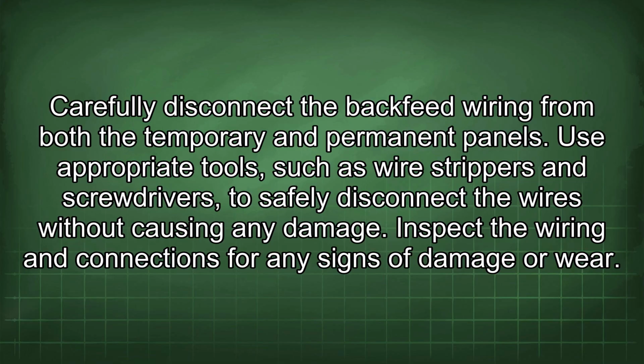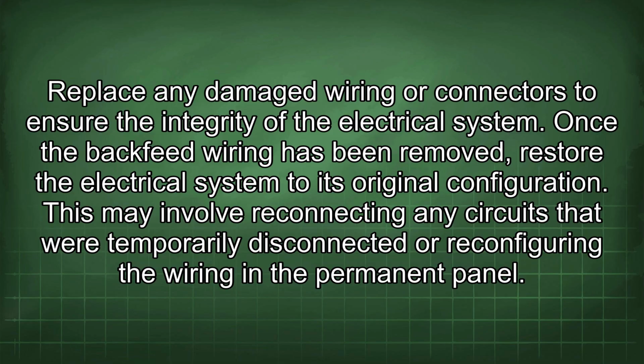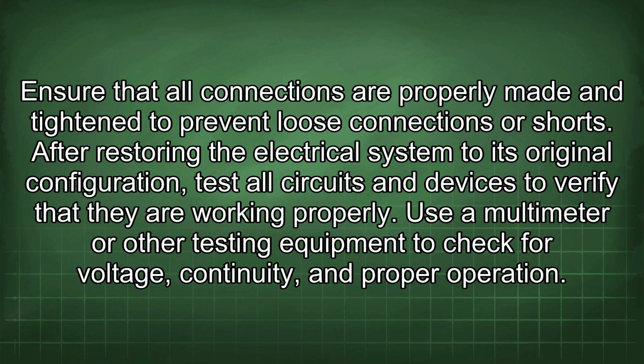Inspect the wiring and connections for any signs of damage or wear. Replace any damaged wiring or connectors to ensure the integrity of the electrical system. Once the backfeed wiring has been removed, restore the electrical system to its original configuration. This may involve reconnecting any circuits that were temporarily disconnected or reconfiguring the wiring in the permanent panel. Ensure that all connections are properly made and tightened to prevent loose connections or shorts.